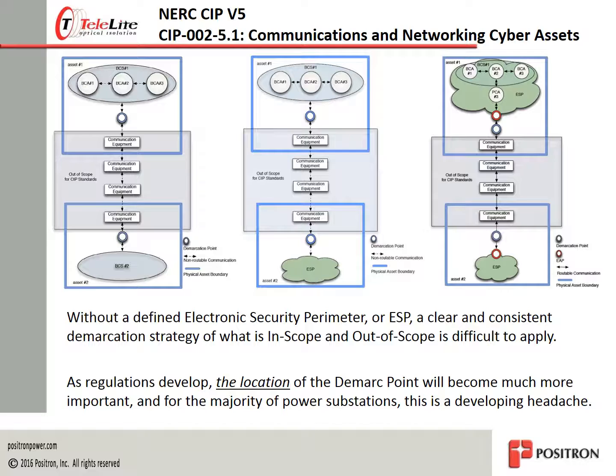The different criteria laid out for communications demarcation are not easy to apply in view of the lack of a defined electronic security perimeter, or ESP. In each case, though, the equipment owned by the telecom provider interfaces with the power company terminations that are directly connected. Historically, the demarcation point between the two entities was more of a commercial concern rather than a security concern. Consequently, demarcation points were determined more by convenience and expediency than security. This brings us to the difficult situation of trying to bring order to chaos.